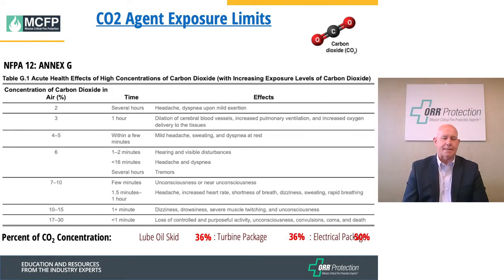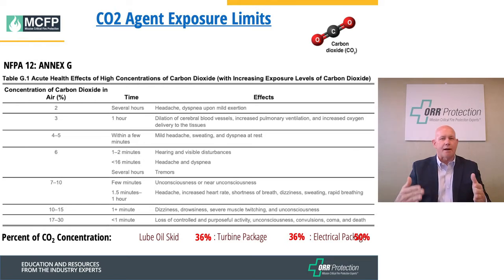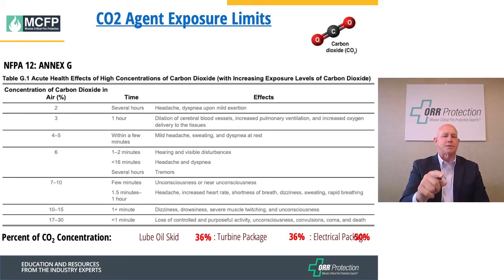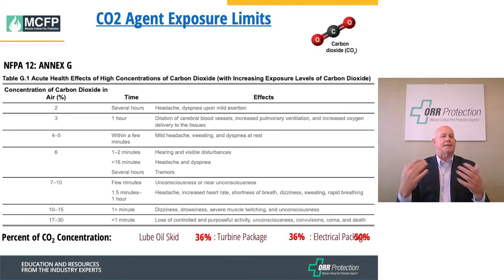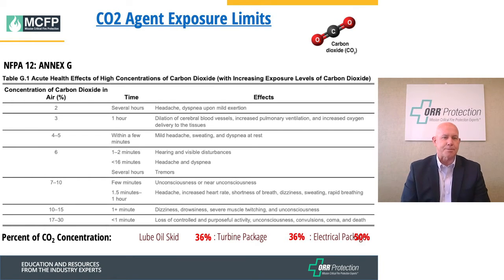Our team members are always taking CO2 exposure risk into consideration when servicing systems — putting flagging tape around and sealing off the area to make sure everybody's protected. Even a minimum of two or three percent CO2 has to be taken seriously. At three percent you'll start getting nauseated, dizzy, and have the possibility of passing out. At six percent you'll start having tremors and headaches.